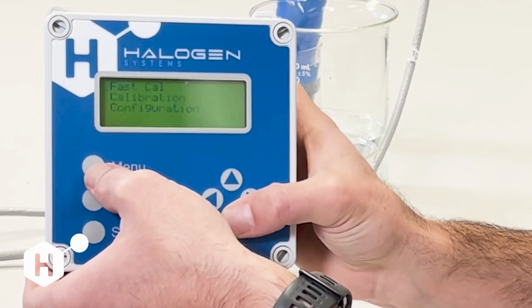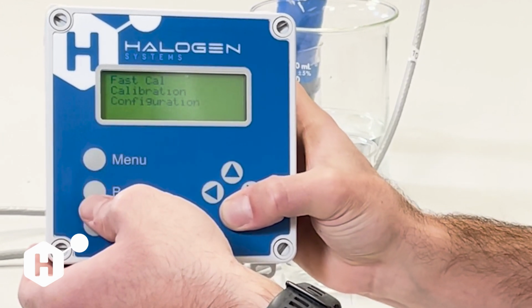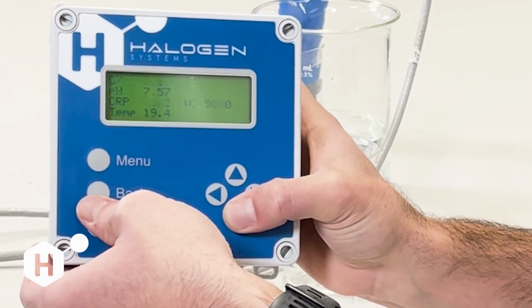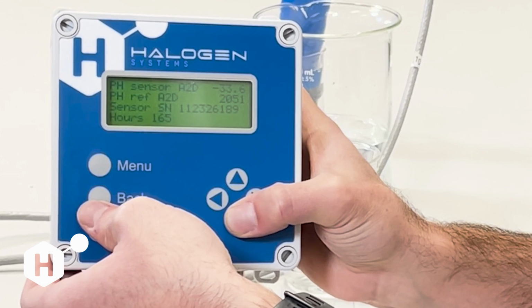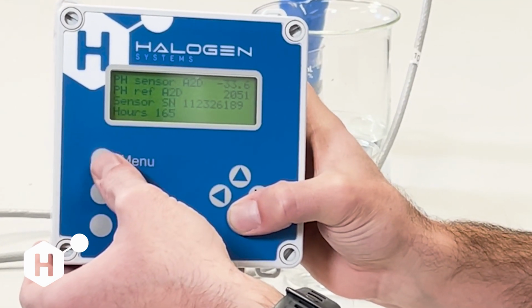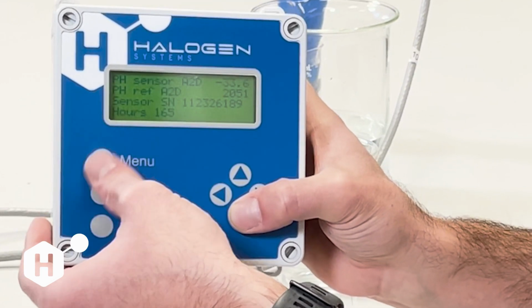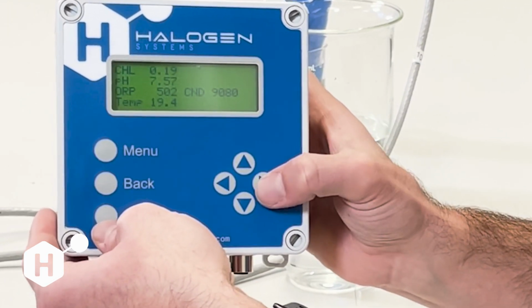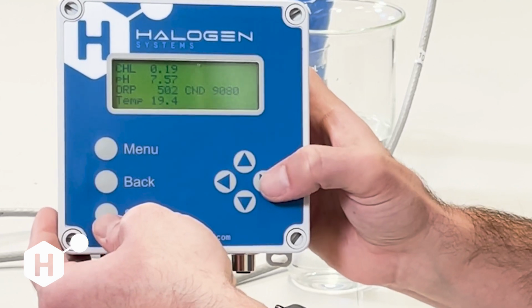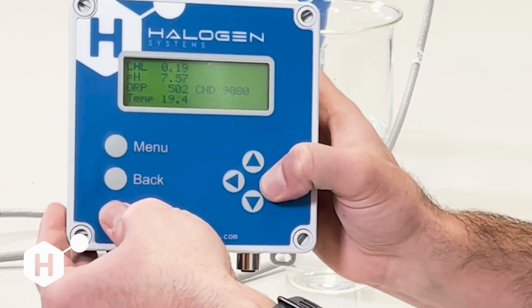And I just saw it change again. And we're at negative 33.6 still. So I'm going to say that this is pretty stable, and we're going to go ahead and do our pH calibration. To do a 2-point buffer calibration, we need to select the long menu by holding select and right arrow.